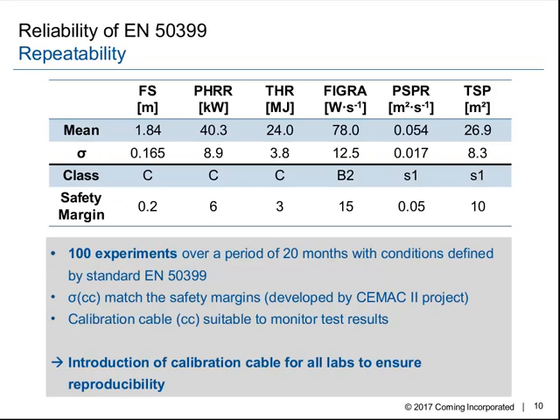What we also see, added below the means, are the sigma values of our parameters. For 100 experiments those sigma values are rather low, and they match perfectly with the safety margins which were defined in prior projects, by the CEMAC II project. Those sigma values and safety margins are in a good match with each other. So this calibration cable is suitable to monitor test results. It's also suitable to monitor your repeatability, for example whether your equipment is still performing in the same way as it was last year.